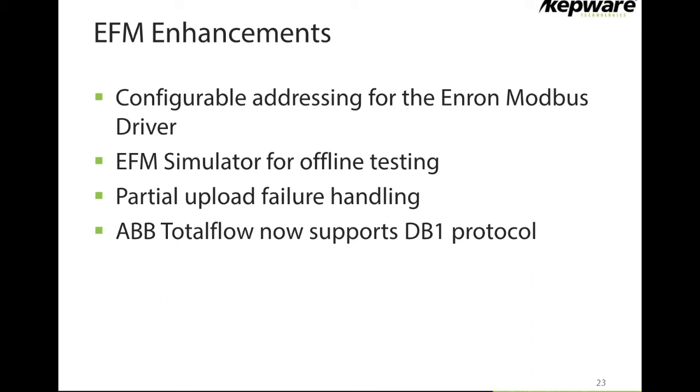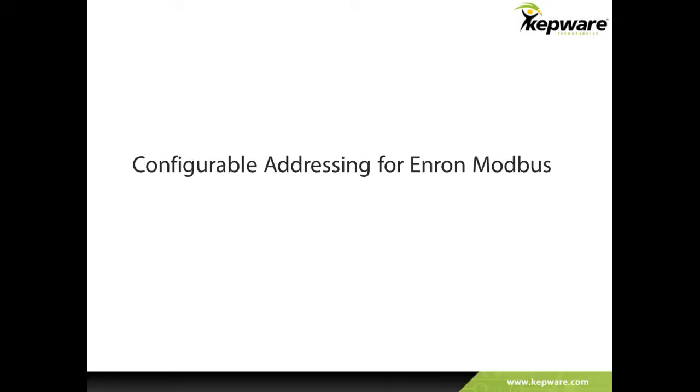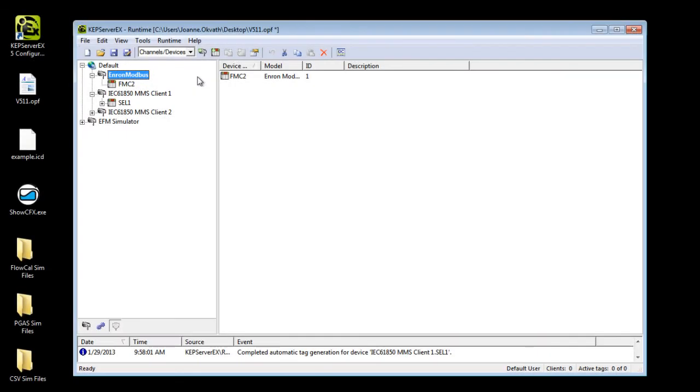The driver for devices that support the Enron Modbus protocol was introduced to KepServer EX V5.9 release. The original Enron Modbus specification defines set address ranges for each data type, but with our 5.11 driver this is now completely configurable by users. Start and end addresses for data type ranges may be managed in the Address Ranges tab in the Device Properties window.